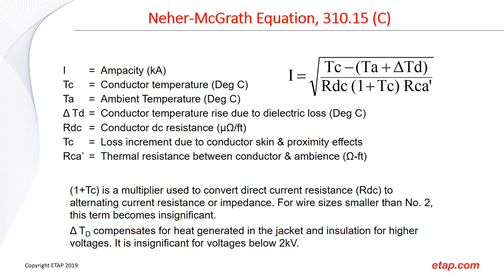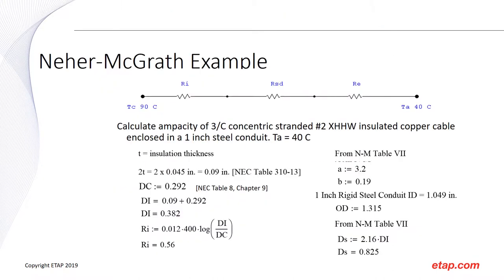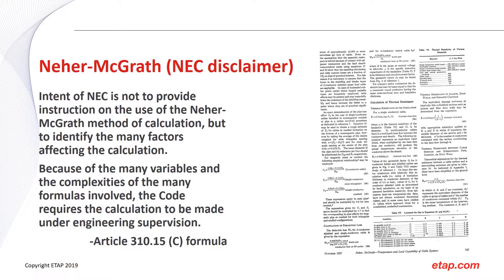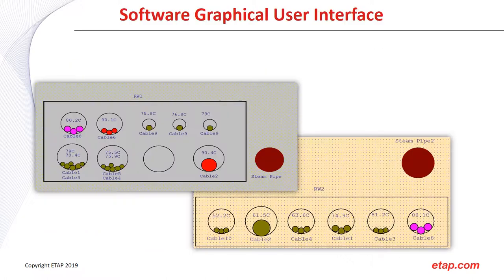For example, to calculate the ampacity of a three-conductor concentric XHHW-insulated copper cable enclosed in a one-inch steel conduit with an ambient temperature of 40°C, you would have to consider many different constants — referring to the Neher-McGrath paper for insulation thickness and several tables. It's a very time-consuming and labor-intensive process. Typically, engineers perform these calculations using a software graphical tool like ETAP.